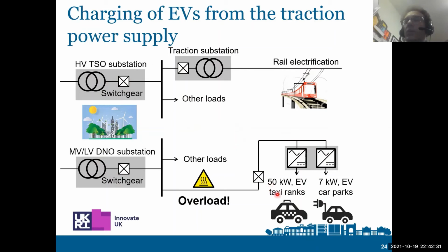The problem is when we add new charging stations, especially rapid chargers with power of 50 kilowatts or more, there is a risk of a lack of capacity at the existing node. Sometimes it's fine to add this charger, sometimes there is a need to upgrade the line, meaning more cables, more transformers, digging up the ground, and expensive work.